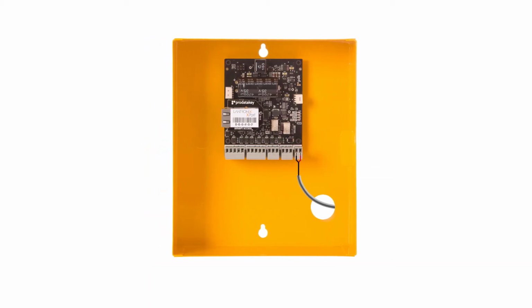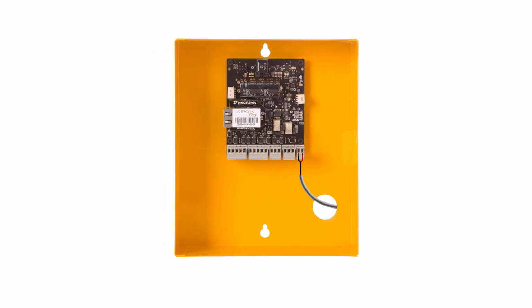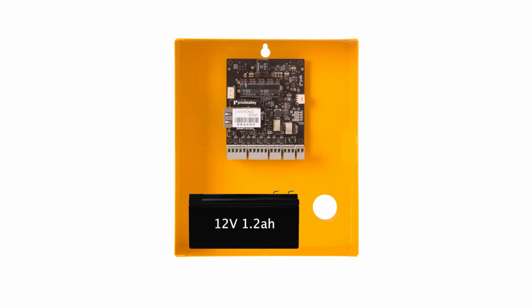The single I/O accepts 12 to 24 volts AC or DC, however, it is most common to use the included transformer to power the controller. Connect the 18-2 wire from the controller to the transformer. Attach the red wire to positive and the black wire to negative. It's always important to install a backup battery. The recommended battery for a single I/O is a 12-volt 1.2 amp-hour battery. Simply plug the battery leads onto the correct battery terminals and backup power has been installed.